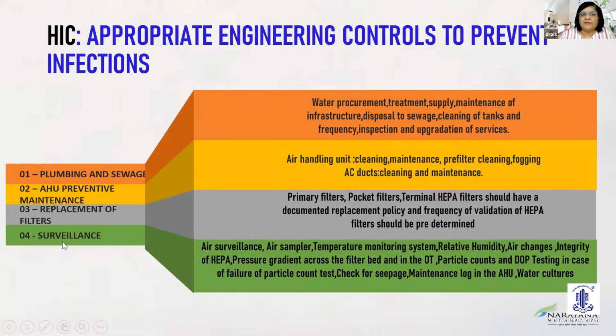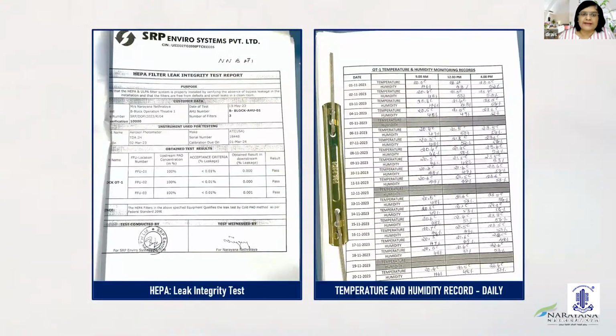Surveillance, again, is a very important part of engineering controls. Air surveillance, air sampler, temperature monitoring system, relative humidity, air changes, integrity of HEPA, pressure gradient across the filter bed, and in the OT, particle counts and DOP testing. In case of failure of the particle count test, check for seepage, the maintenance log in the AHU, and the water cultures. All of these areas are crucial. They need regular checkups, and a regular report should be given to the HIC committee or whatever internal committees you have, so that tight control can be kept for the safety of patients and medical personnel.